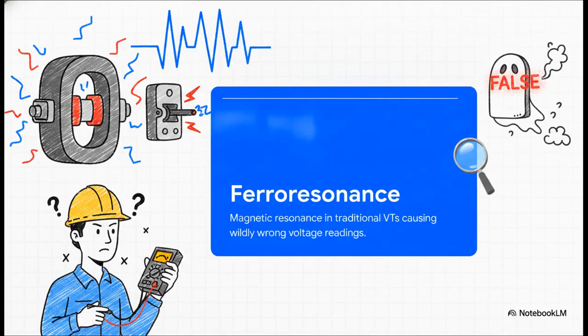But traditional VTs have a bit of a dark side, and it's a massive pain point for marine electrical engineers. It's this phenomenon called ferroresonance. Because a traditional VT relies on a heavy iron magnetic core, it's really susceptible to magnetic resonance during switching transients. Basically, when a breaker opens or closes, the sudden shift in the network can cause the VT's core to resonate, and that produces wildly inaccurate voltage readings. This erratic behavior often completely mimics a real electrical fault, sending engineers frantically chasing phantom faults while pulling their hair out over problems that don't actually exist in the primary system.